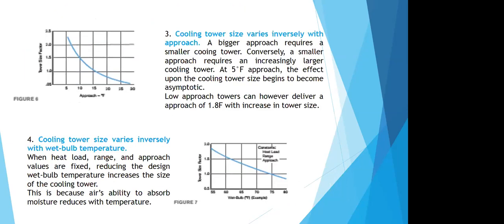Third point about the size of the tower is the approach, which I think most of us are familiar with. So the tower size varies inversely with the approach. So the higher the approach, the smaller the tower, and vice versa. So we can see in this chart, say at 15 degree approach, that is the difference between the cooling water outlet temperature and the wet bulb temperature. If it is at 15 degree Fahrenheit, we have a unit size.